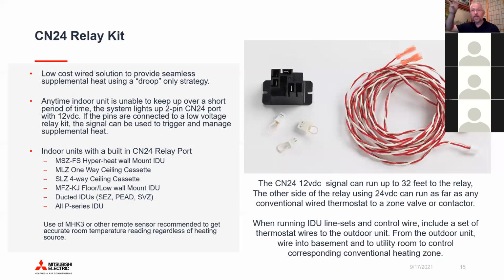Put the relay kit in right at the start, right by the unit, make that a short little run, and then run thermostat wire down to the outdoor unit. And then you've got to go inside, from the basement to get to the panel. That's where in a lot of cases you would just run your thermostat wire for whatever zones are being managed, and just label your wiring and plug them into your zones down there. That way you're not interrupting any additional walls or trying to run thermostat wire in weird chases around the house. You're just using the existing work that you're already doing. So then it's very simple controls. It's all in one place. There's no Wi-Fi interaction whatsoever. And you get, at least in New York State, potentially thousands of dollars to support the labor involved in including a couple of thin wires with your existing installation.